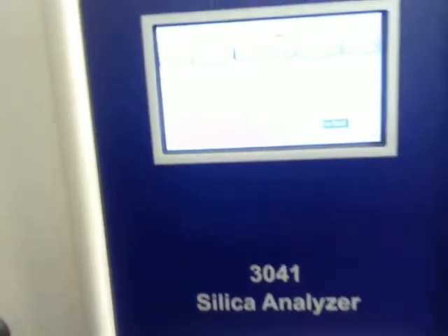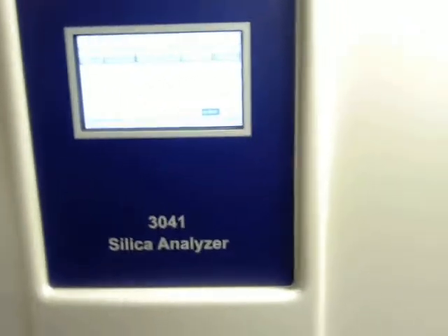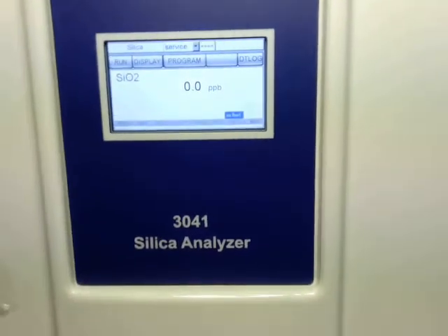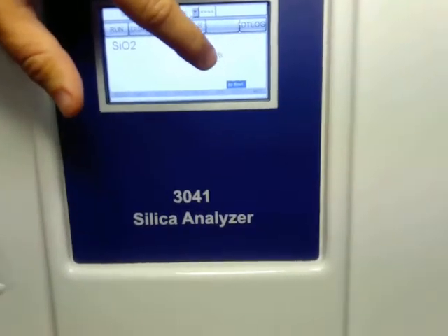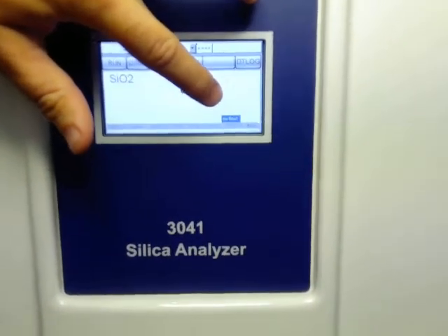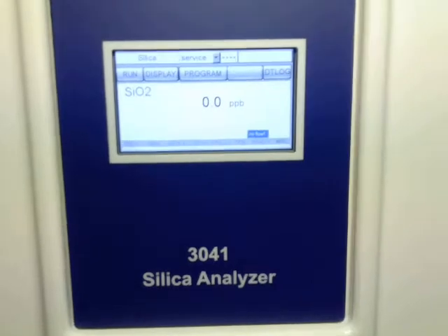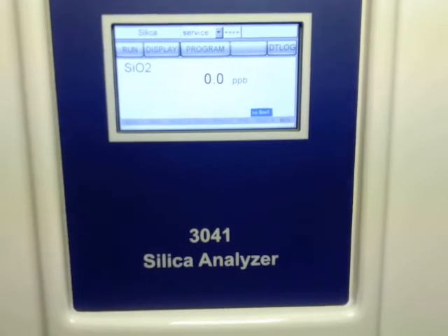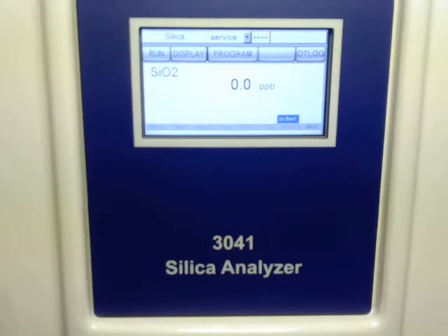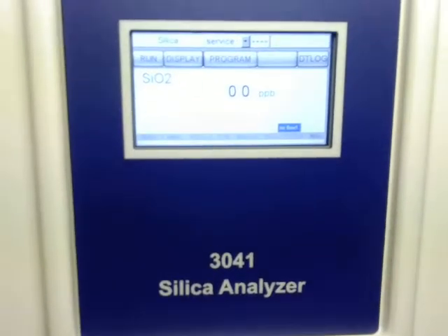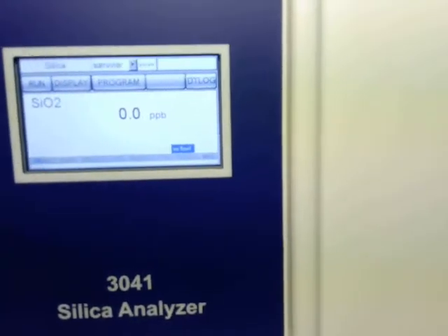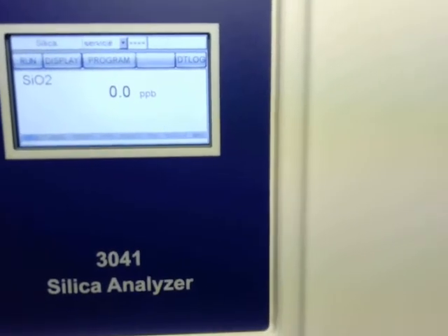And once that's in, and now since we don't have any flow, if we swap over to look at our screen real quick, we'll see that a no flow alarm popped up on our screen. And again, if the analyzer was in the middle of taking an analysis, it would finish the one it was doing, and then when it came time to start a new one, it would not start and go into standby. For now, we'll disconnect it because we want to pretend that we have sample, and that alarm goes away.